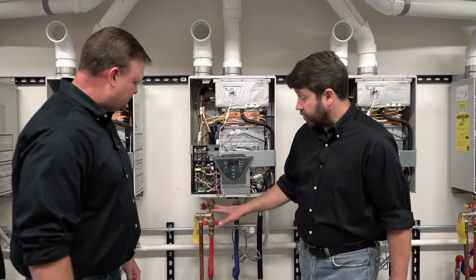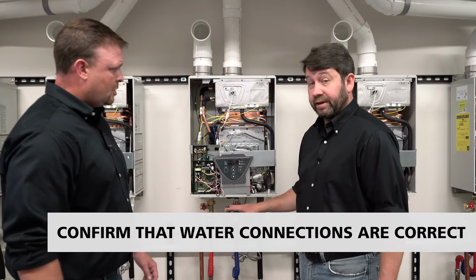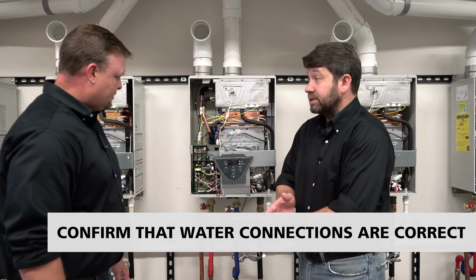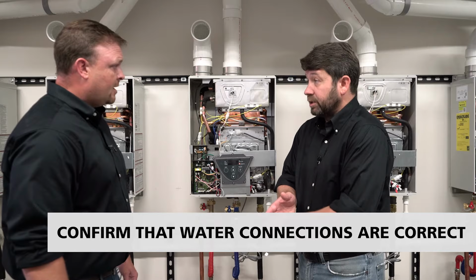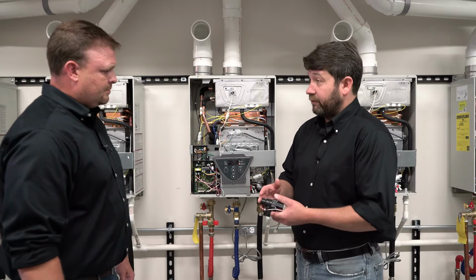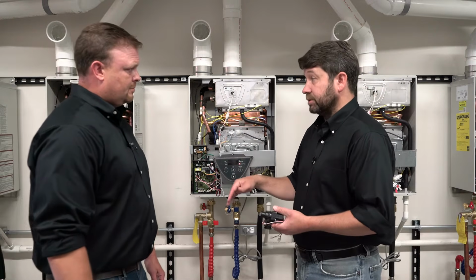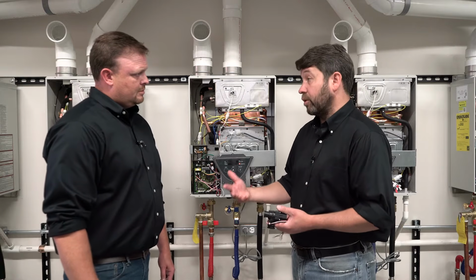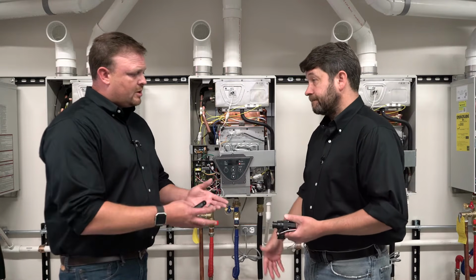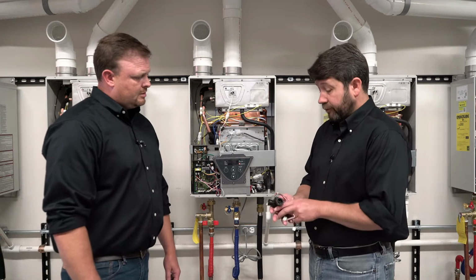The first thing is definitely make sure that the hot and cold are connected correctly, because if we connect those in reverse, and it's easy to do sometimes when you get in a rush, water will still flow through the heater, but the flow sensor will only detect flow if it's flowing in the proper direction. And so if it's backwards, it's not going to detect flow and the water heater won't operate. Okay, and that's because of the way the flow sensor is designed? That is, it's the way the flow sensor is designed.